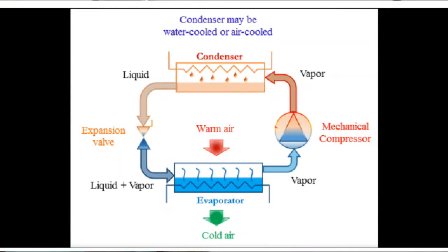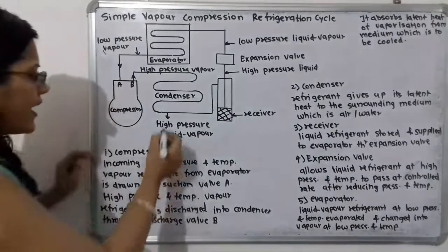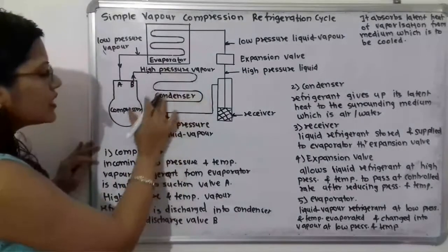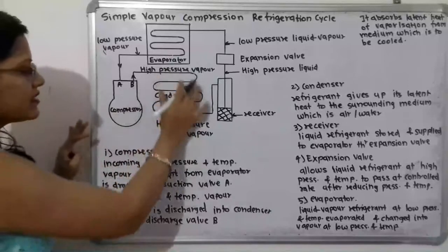In the condenser, the refrigerant gives up its latent heat to the surrounding medium, which is air or water. Latent heat means the heat involved in a phase change. Here the refrigerant is in vapor form, so when it gives up its latent heat, this vapor is getting converted into liquid or a liquid-vapor mixture.